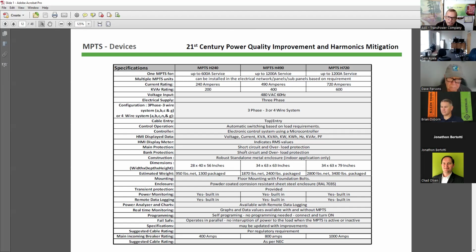MPTS has built-in short circuit and overload protection. It has metering—more metering than utility meters or utility smart meters can even comprehend. So this is actually taking care of a lot of things, and it does automatic switching based on load requirements, which means you don't need software people, IT, or programmers to touch the MPTS or do anything with it. It's pre-programmed, self-learning, built so that once you turn it on, you leave it alone for the next 30 years.